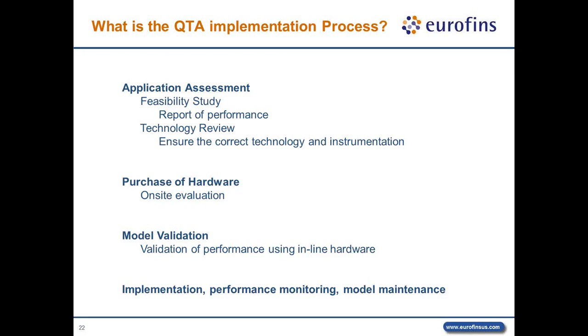QTA services include daily spectrometer performance monitoring by reviewing the spectra and the diagnostic information. This allows us to determine when preventative maintenance should be performed. It reduces downtime and provides the opportunity to have replacement parts on site and available for service rather than reacting in the event of a failure. If there is a process change or the addition of a new raw material supplier, we perform any necessary modeling work to the existing models as part of the QTA services at no additional charge.